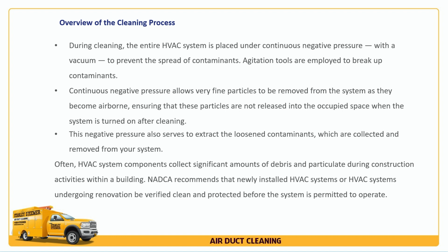Negative air is the most important part of this. When the whole system is under negative air, whether on the return side or the supply side, when we clean a section, that entire area has to be under negative air while we're going through there, because you need things to go to your vacuum and get removed from the building.